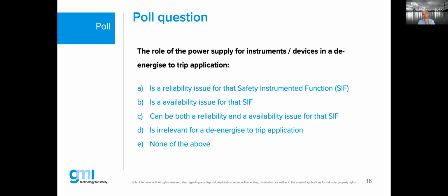We only have 13% saying it is irrelevant for the de-energized to trip application. And although it's only 13% of the people who came to the webinar today, I can say that irrelevant for the de-energized to trip application is a very common misunderstanding of the functionality of the power supply. If I were very brief with you, I would say yes, you can say de-energize to go to safe position, the role of the power supply is not relevant. I would say many people make that mistake in thinking, and I will say why this is a mistake. That is why the answer can be both a reliability and also an availability issue. That is the most correct and also the most complete answer.